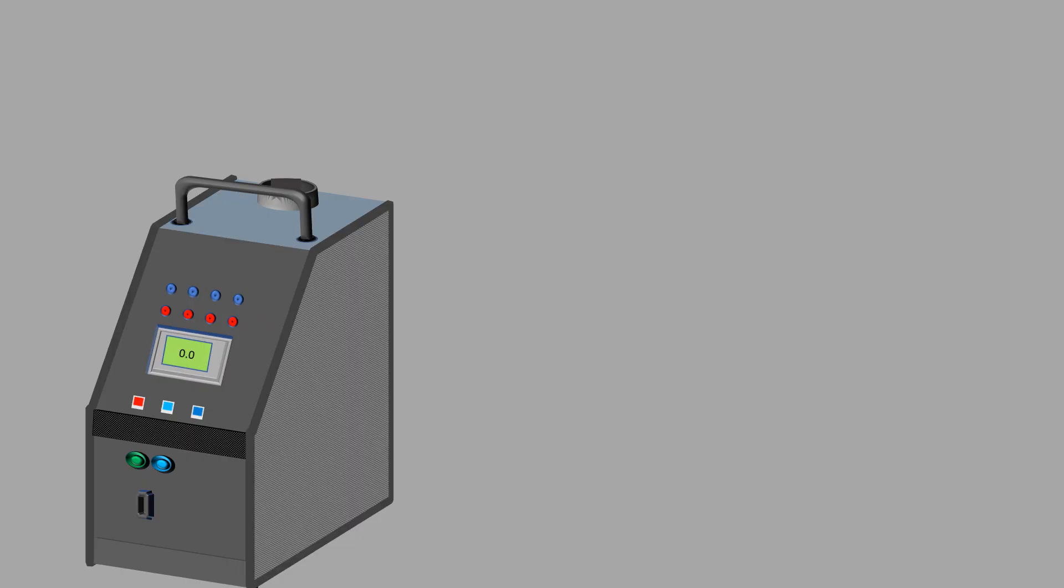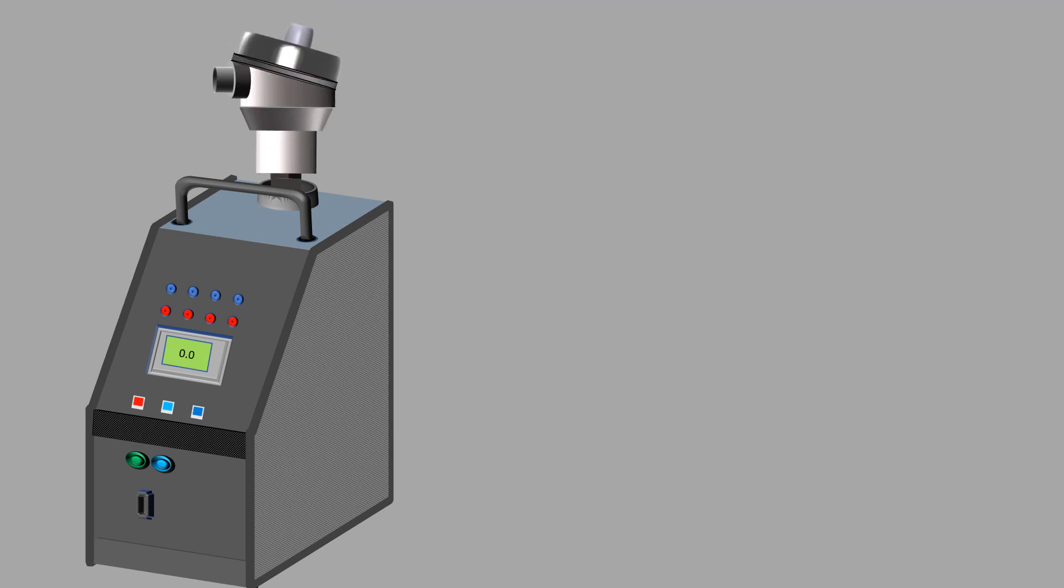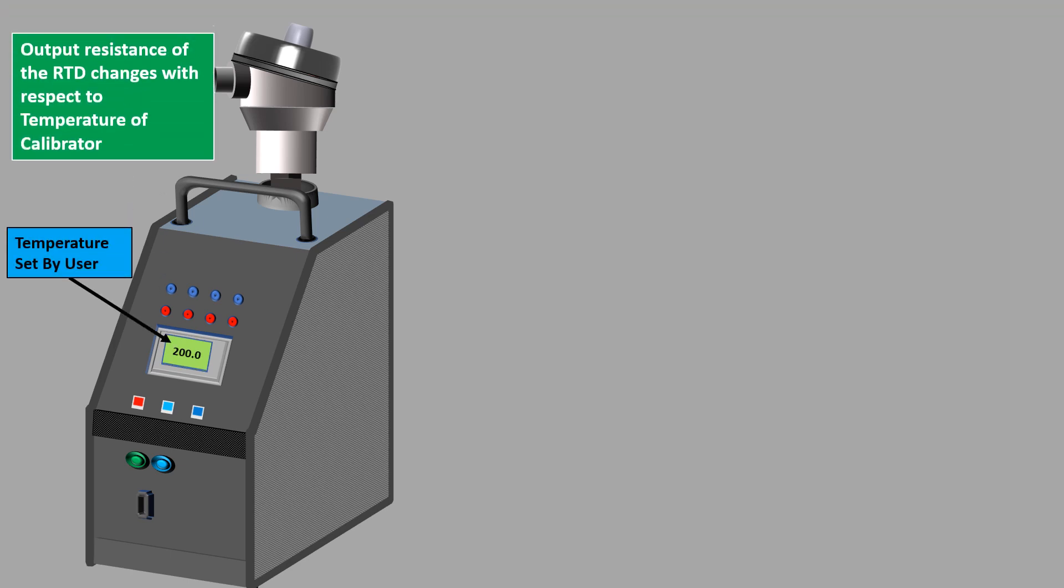To perform RTD calibration, usually a dry block calibrator or temperature bath is used as calibrator. The RTD which is to be calibrated will be placed into the temperature calibrator. The calibrator maintains a fixed temperature which is set by the user and so the output resistance of the RTD changes with respect to the temperature of the calibrator.